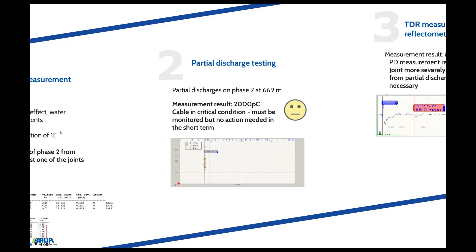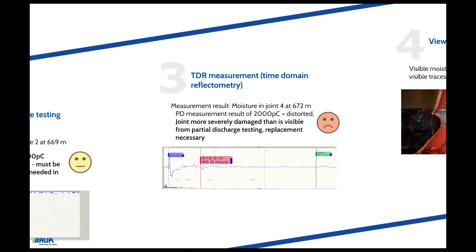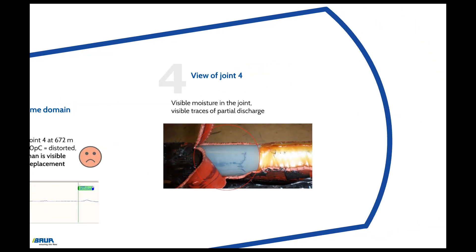Only by overall consideration of the results, together with the dissipation factor measurement, can the condition of the cable be determined. The TDR measurement, which is also used for the location of damp joints, shows that the moisture in joint 4 lies at 672 m. The fault location identified in the example coincides with that from partial discharge testing. The partial discharge measurement of 2000 pC is therefore a distorted result caused by the moisture in the joint. The joint is more severely damaged than can be seen from the partial discharge testing and should be replaced immediately to prevent a failure during operation. The subsequently exposed joint exhibits clear traces of partial discharges as well as moisture, confirming that the decision to replace the joint immediately was appropriate.